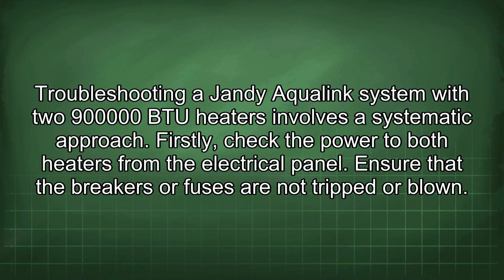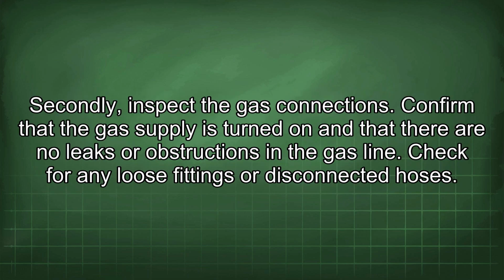Troubleshooting a Jandy Aqualink system with two 900,000 BTU heaters involves a systematic approach. Firstly, check the power to both heaters from the electrical panel. Ensure that the breakers or fuses are not tripped or blown. Secondly, inspect the gas connections. Confirm that the gas supply is turned on and that there are no leaks or obstructions in the gas line. Check for any loose fittings or disconnected hoses.